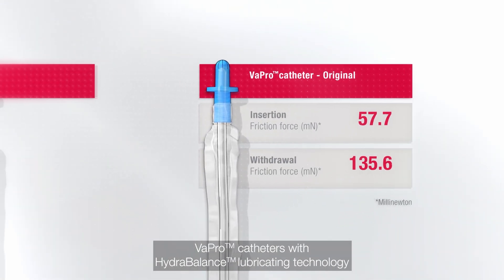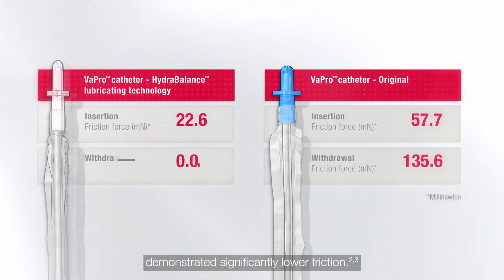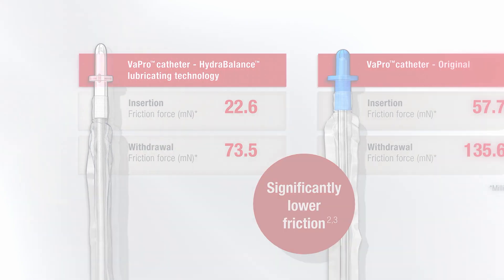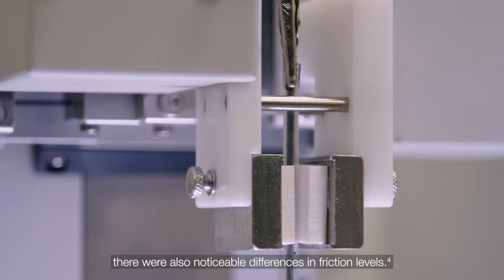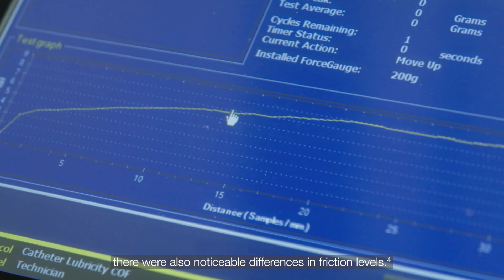What are the results? Compared to the original Vapro catheter, Vapro catheters with HydraBalance lubricating technology demonstrated significantly lower friction. Compared to catheters from other manufacturers, there were also noticeable differences in friction levels.